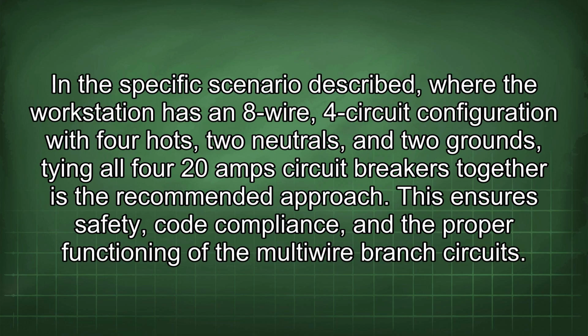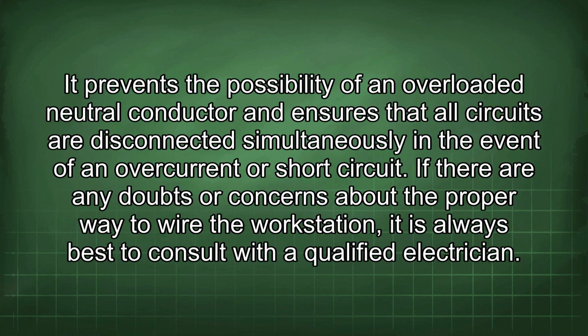In the specific scenario described, where the workstation has an 8-wire, 4-circuit configuration with 4 hots, 2 neutrals, and 2 grounds, tying all 4 20-amp circuit breakers together is the recommended approach. This ensures safety, code compliance, and the proper functioning of the multi-wire branch circuits. It prevents the possibility of an overloaded neutral conductor and ensures that all circuits are disconnected simultaneously in the event of an overcurrent or short circuit.